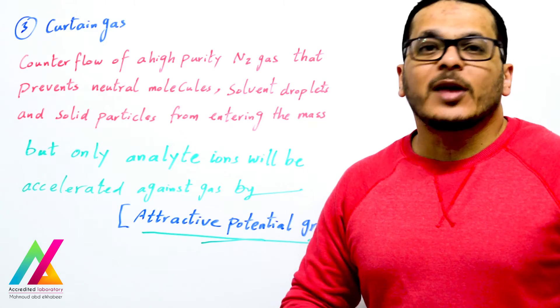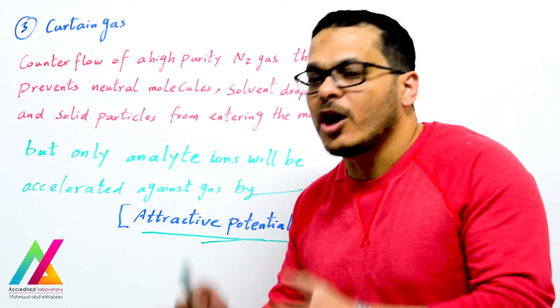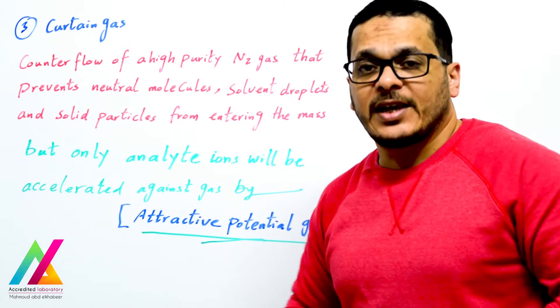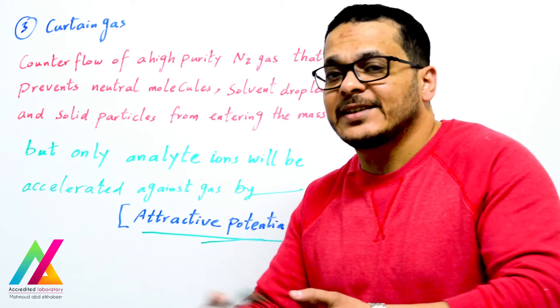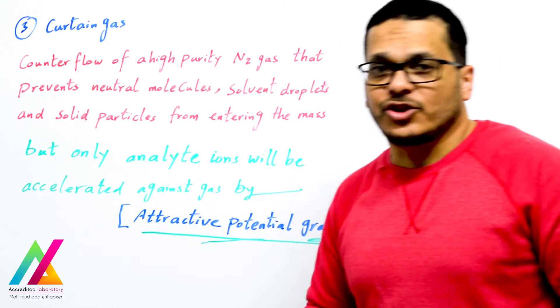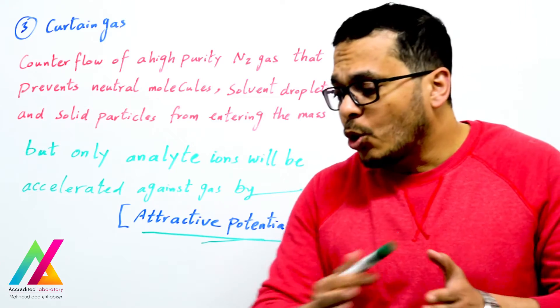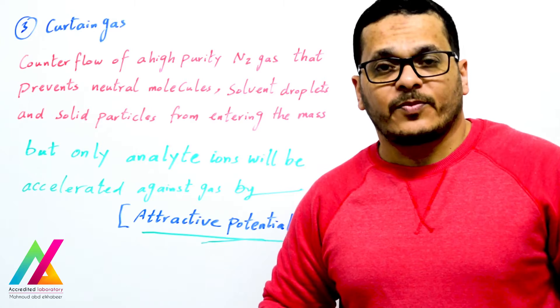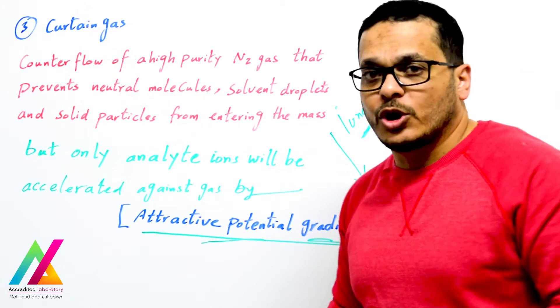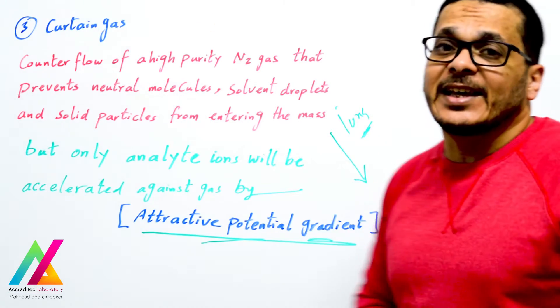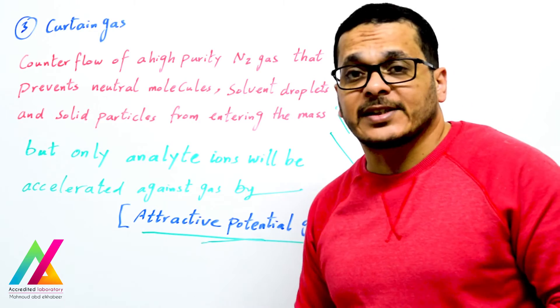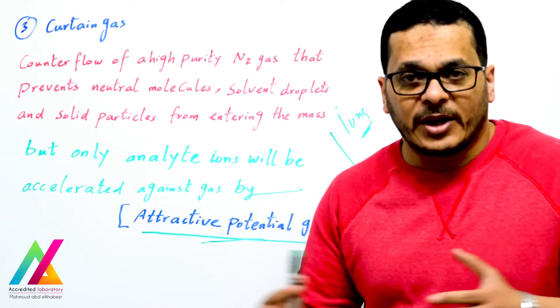Curtain gas is a counter-flow of high-purity nitrogen gas that prevents neutral molecules, solvent droplets, and solid particles from entering the mass analyzer. Only analyte ions will be accelerated against the gas to the mass analyzer by an attractive potential gradient — meaning potentials applied to all parts of the mass spectrometer, from ion source to detector, decrease gradually to help ions transfer to the detector. The name 'curtain gas' is used in AB Sciex instruments; in Agilent instruments, for example, it is called 'drying gas.' The name differs between instruments but the function is the same.